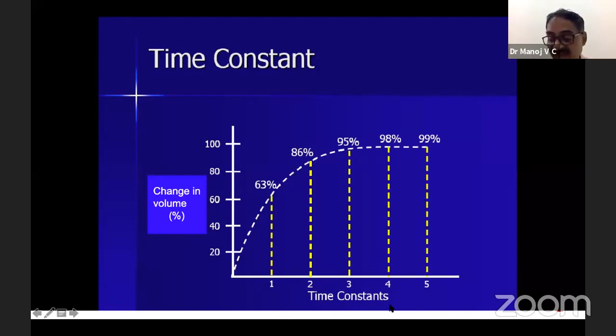But if you use 5 time constants as the time required, then there are some problems. I'll tell you what the problem is. Let's look at a healthy term neonate who has a compliance of 4 ml per centimeter of water and a resistance of 30 centimeters of water per liter per second. So the time constant in a healthy term neonate is 0.12 second. So 5 times this means you have to use 0.60 seconds to push in air.